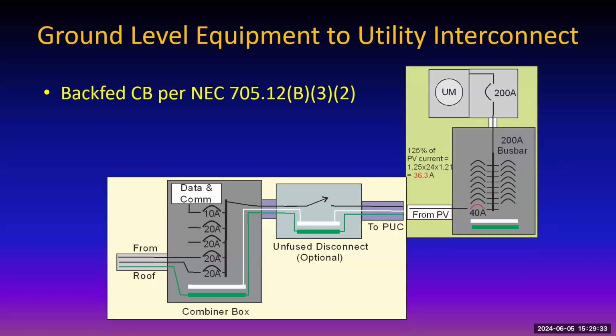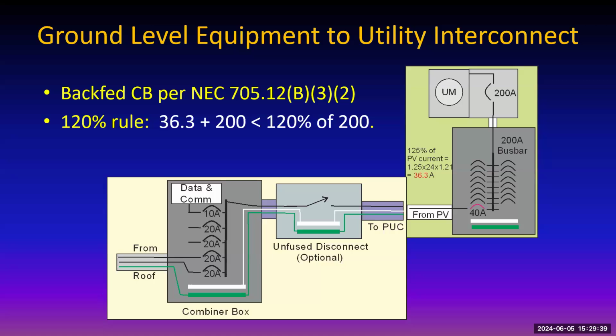NEC 705.12(B)(3)(2). This is called the 120% rule. And it says that the sum of 125% of the inverter outputs, that's the 36.3, plus the rating of the main circuit breaker, the 200 amp, must be less than 120% of the rating of the main bus bar. Well, 120% of 200 is 240, and 236.3 is less than 240, so we're good. So this is an okay way to do the interconnect.